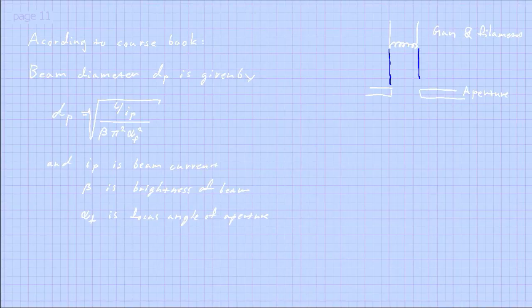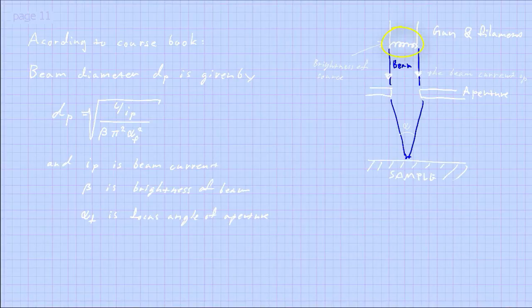The brightness of the source also governs this. Brightness is defined as the intensity of the source divided by the area creating that emission. For example, a tungsten filament is a large metallic wire that glows and emits electrons over a rather big illuminating area. A field emission unit looks more like a small needle, and electrons are emitted only from the outermost tip, so all intensity comes from a very small region. The field emission source has a brightness about 1,000 times larger than the tungsten source.